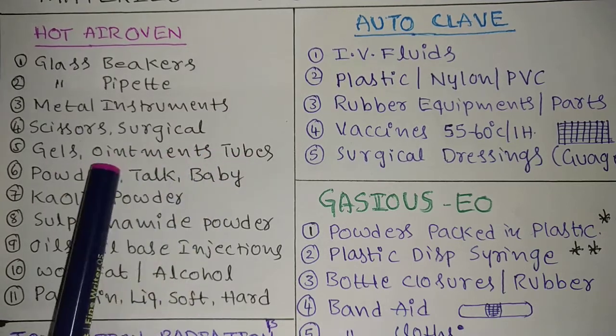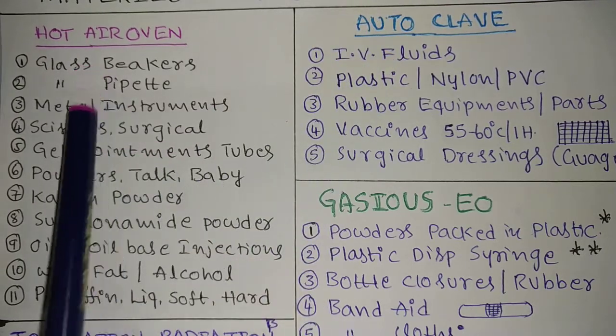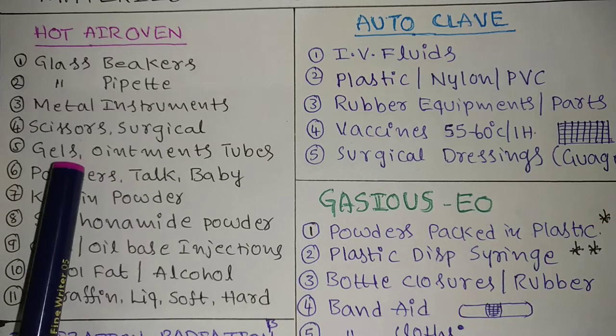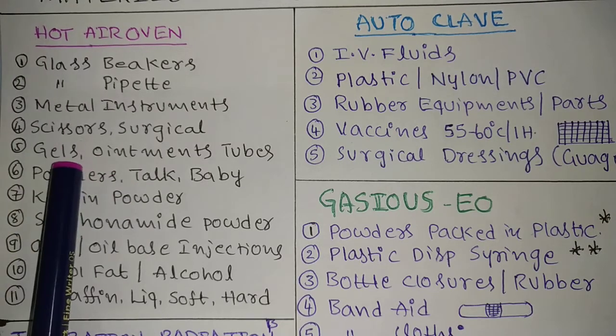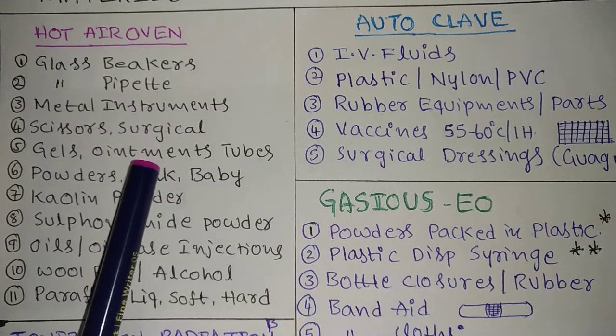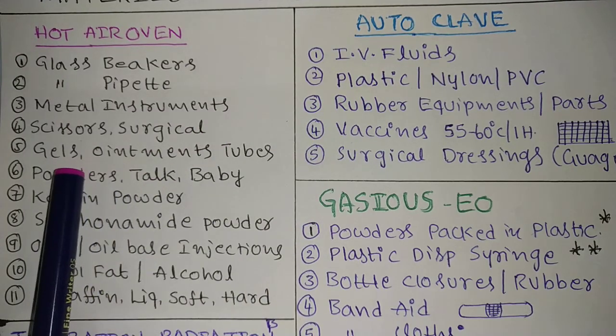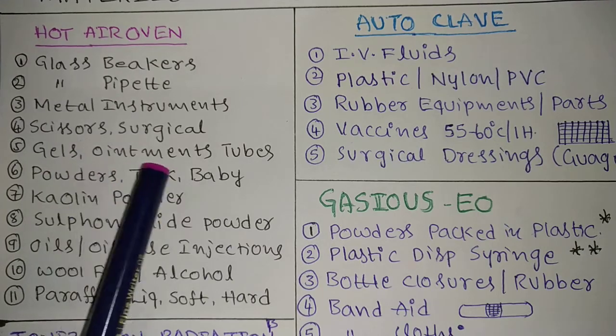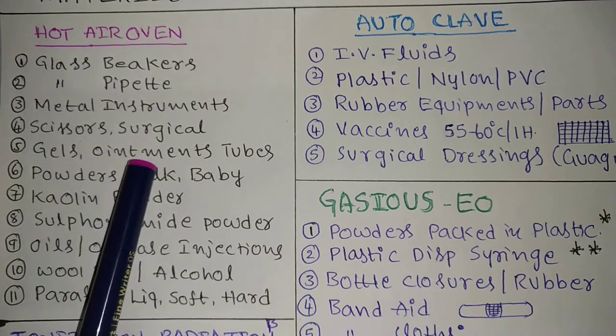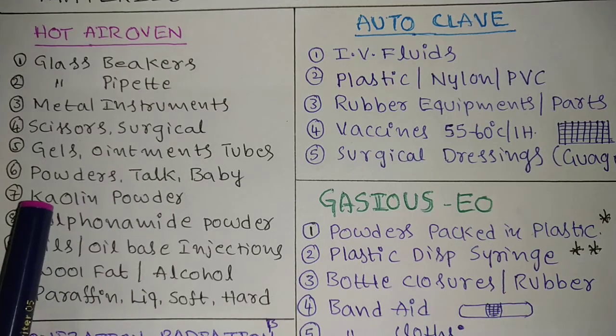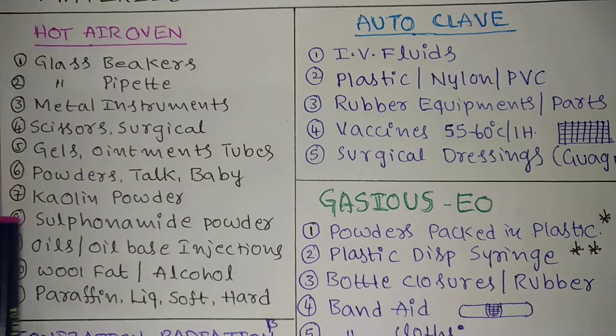Gels and ointments — ointment tubes also should not go into the autoclave; use the hot air oven only. Because for gels and ointments, if they absorb moisture or water, there is a chance of changes in the formulation — they will liquefy. That's why the hot air oven is preferable for gels and ointments.